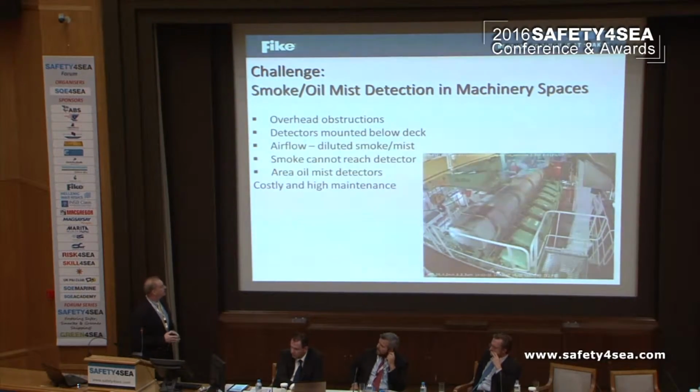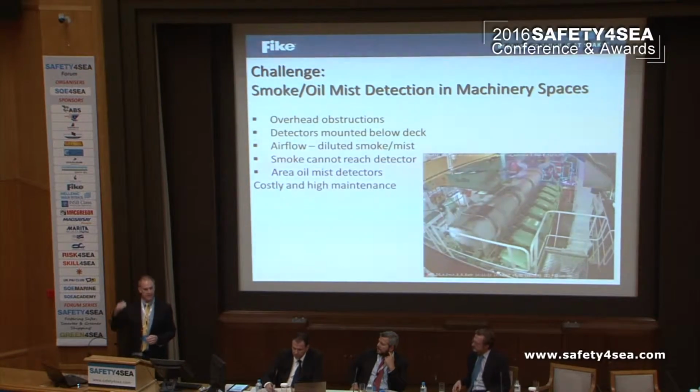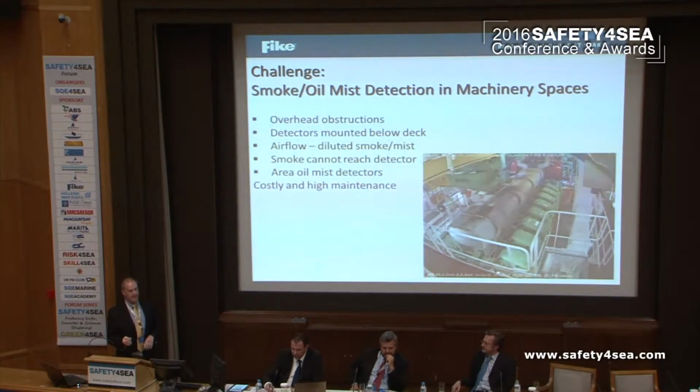So notice the video. This is an exhaust leak, so the system can detect not only oil mist but also smoke. In engine room atmospheres, it's difficult to detect smoke because of the airflows and the obstructions in the overhead. Therefore, it's difficult for smoke detectors to detect the smoke. Video analytics is detecting in the entire field of view of the camera. All the pixels are analyzing for a detection.